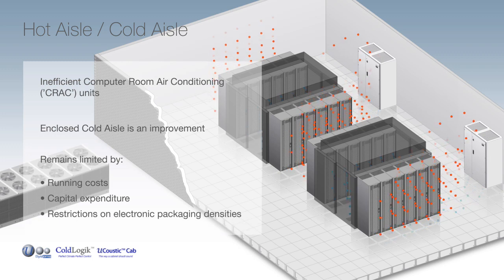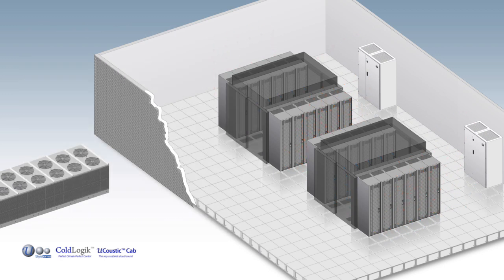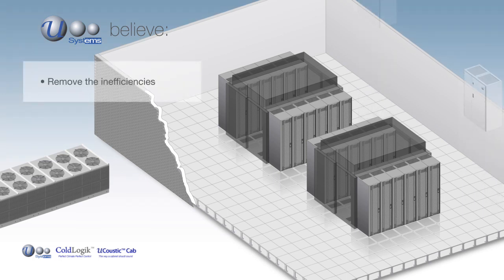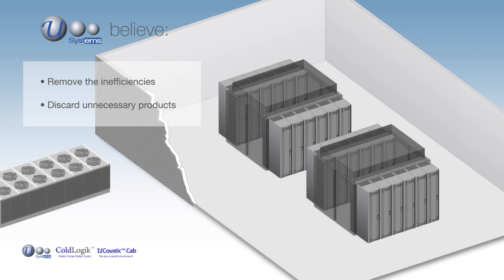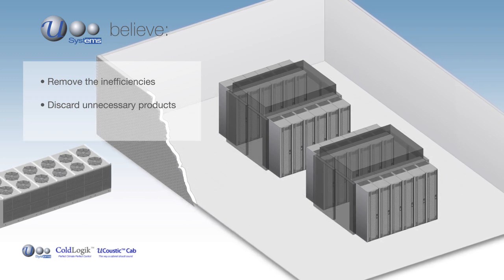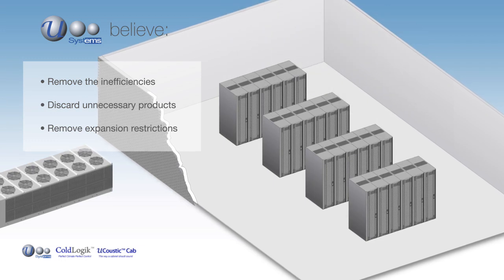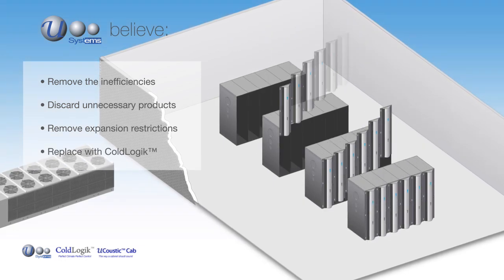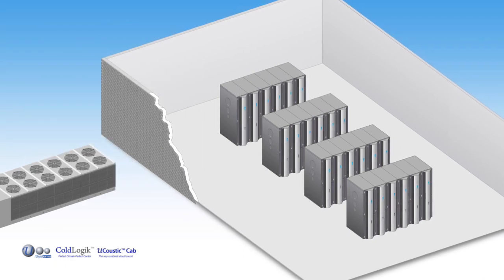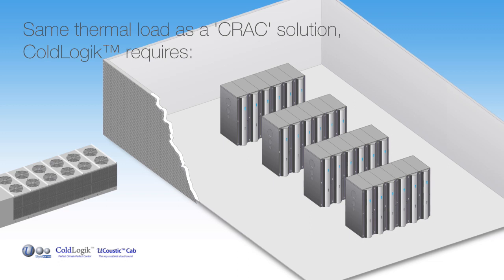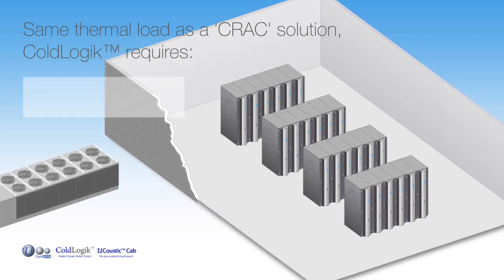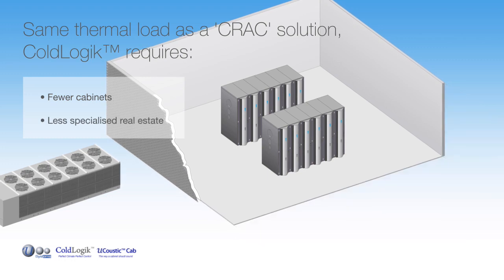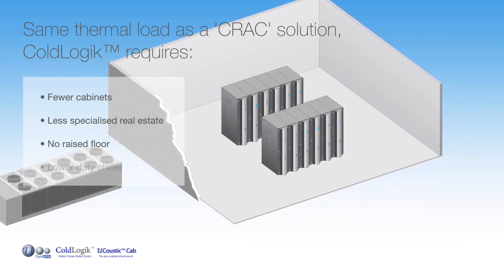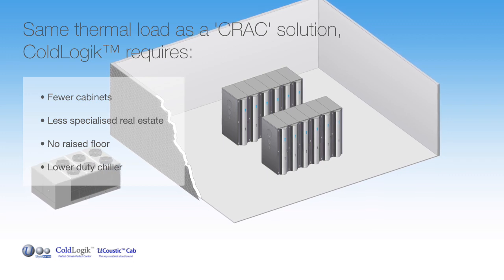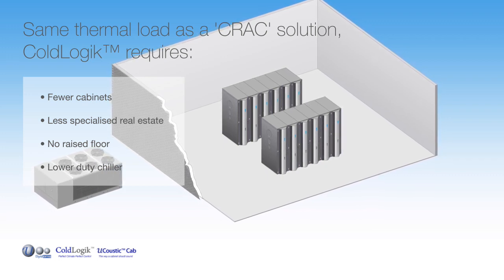When considering the energy strategy for data centers and their associated facilities, the view taken here at USystems is simple. Remove the inefficiencies. Discard unnecessary products and the associated capital expenditure. Remove expansion restrictions. And replace them with an efficient cooling solution. When you consider that to achieve the same thermal load as a traditional CRAC solution, ColdLogik requires fewer cabinets, less specialized real estate, no raised floor, and a lower duty chiller, the benefits of the USystems data center model and the potential for reduced capital expenditure are in plain sight.